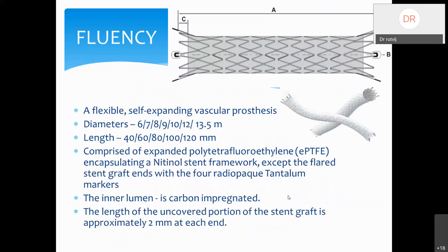Discussing the Fluency endograft briefly: it is a flexible, self-expanding vascular prosthesis available in a variety of diameters from 6 up to 13.5 mm and lengths of 40, 60, 80, 100, and 120 mm. It is comprised of expanded polytetrafluoroethylene (ePTFE) fabric encapsulating a nitinol framework, except at the flared edges at both ends, which have radiopaque tantalum markers. The inner lumen is carbon-impregnated, and the length of the uncovered portion of the stent graft is approximately 2 mm at each end.